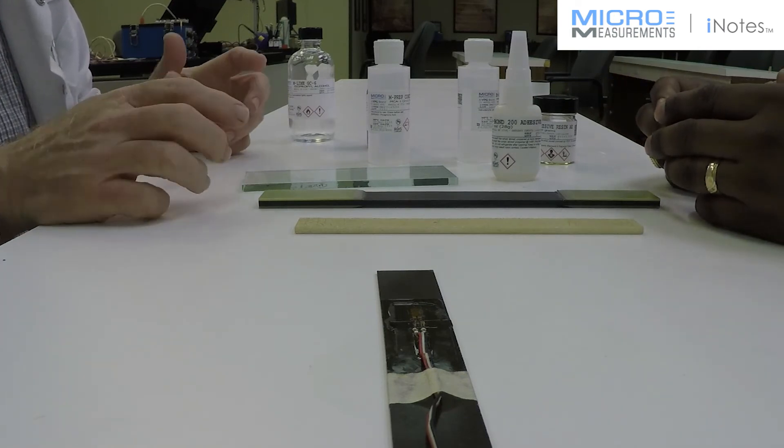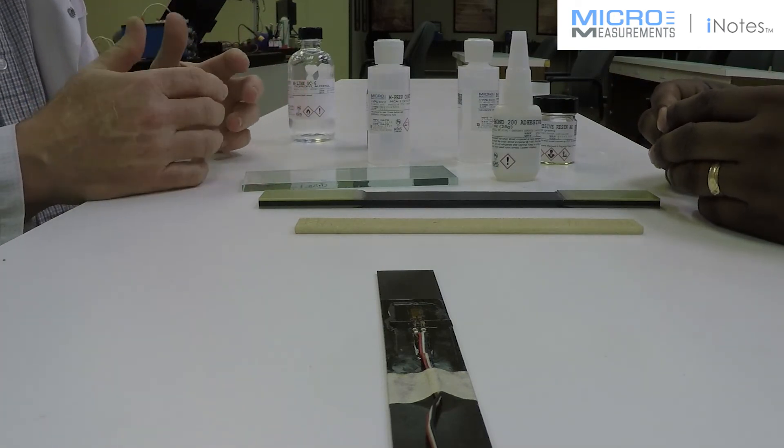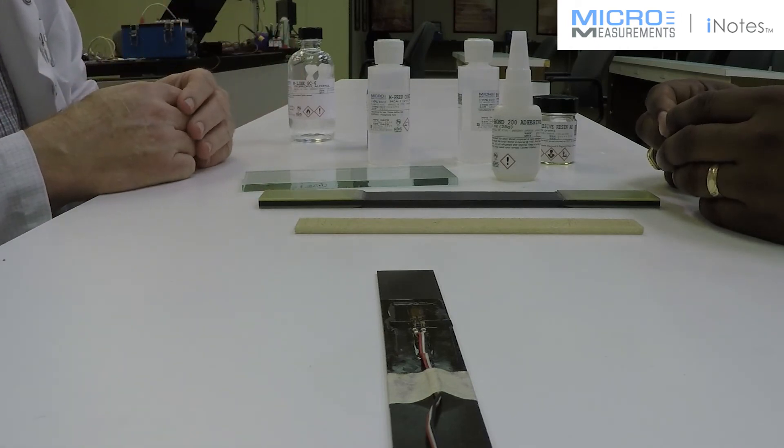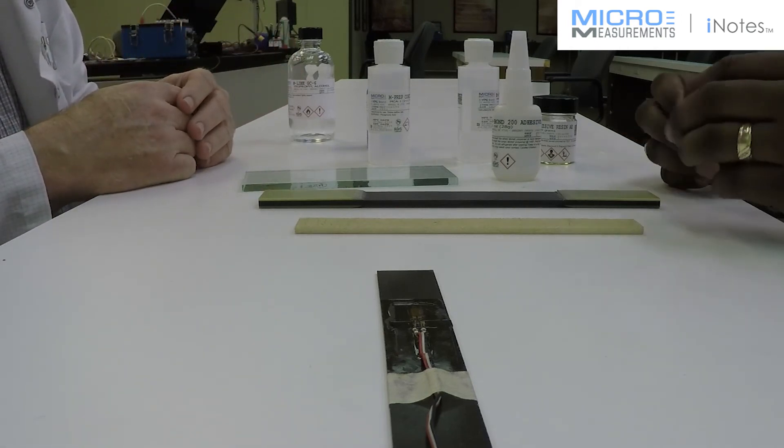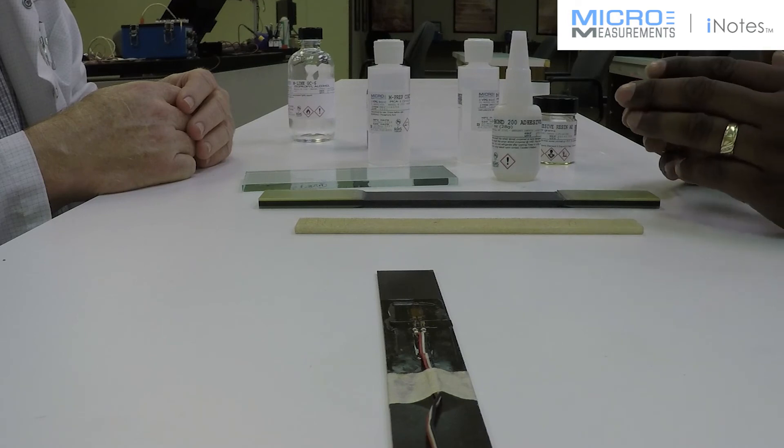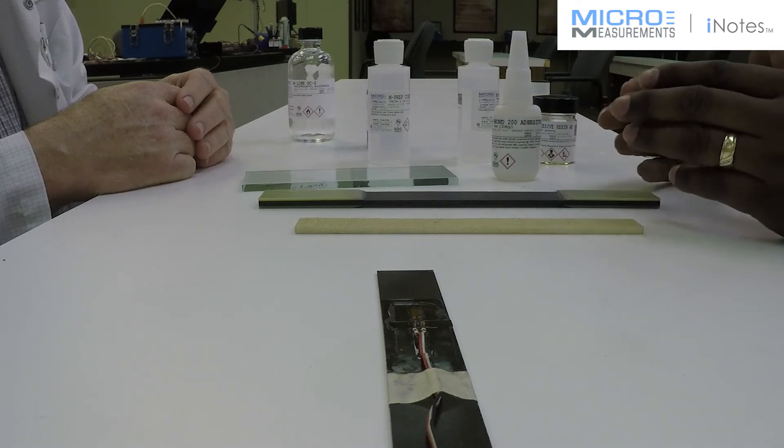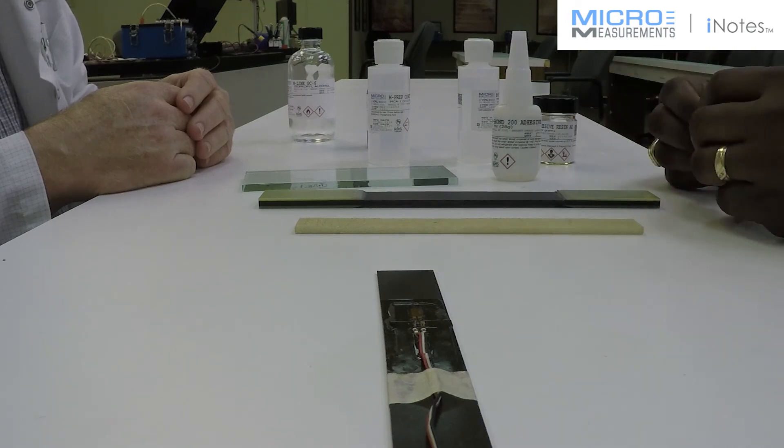What about the size of the strain gauge? How big a gauge or how small a gauge should I use on my composite material? Right. In terms of composites, we generally want to go with a gauge that has a pretty good averaging capability. So that would be something on the order of an eighth inch or a quarter inch gauge length.